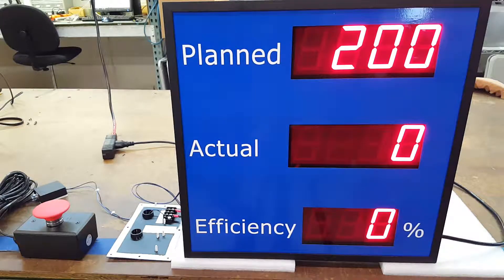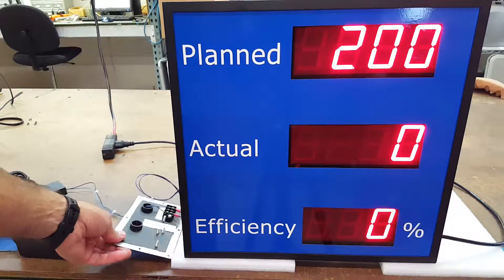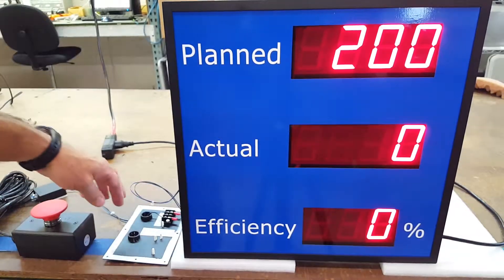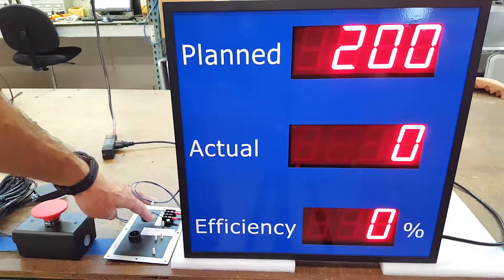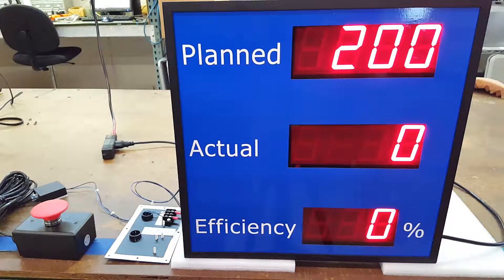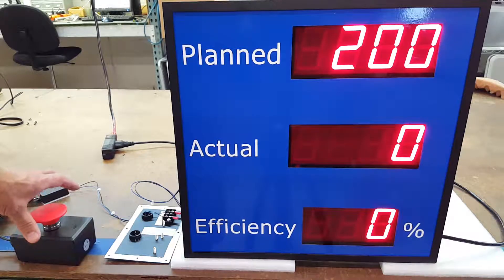To increment your actual count, there is a plate located on the back with terminal blocks. You can connect your contact closure, or this will take a 5 volt to 30 volt DC input pulse. Right now I have it connected to a large 60 millimeter palm switch.